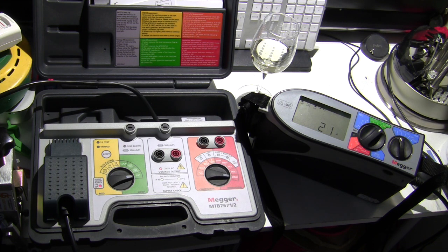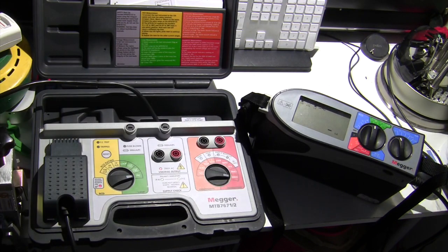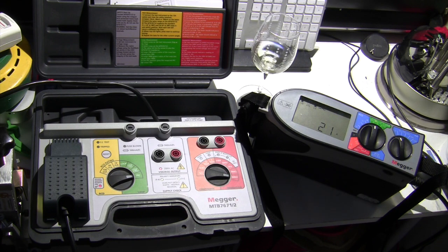Again, may not be the kind of numbers you'd expect to see, but it's just because we're, like I say, on the end of a long extension lead here. But as long as the Fluke and the Megger both give me the same sort of reading, that's okay. If I do the PFC no trip setting, again, I should get that same sort of number again, somewhere around 21 amps. Wait for it. Blimey, it's enough to drive you to drink. Ah, yeah, there we go, 21 amps, jolly good.